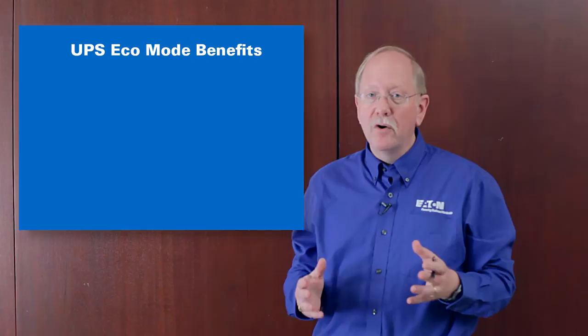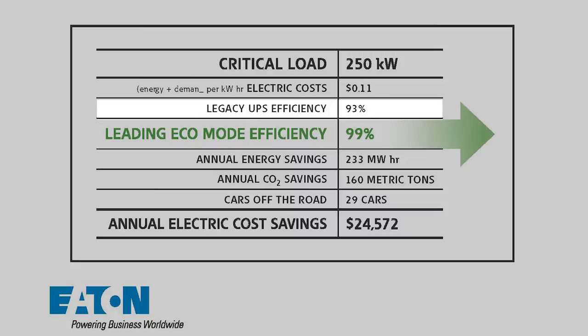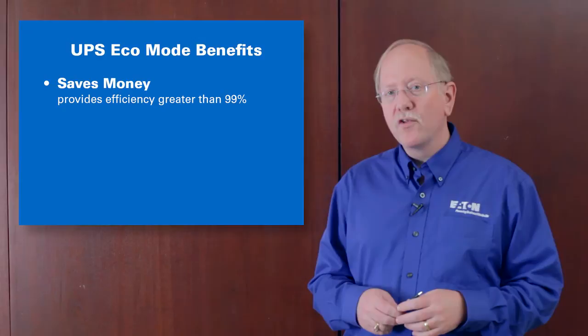The main reason for having eco mode is saving money. So, just as an example, let's take a look at a medium-sized UPS. Here we have a 250 kilowatt UPS, compared against a legacy UPS that's 93% efficient, using an eco mode UPS at 99%, and the savings at 11 cents a kilowatt hour are $24,500 per year of operation. Significant savings, and will actually repay the cost of the UPS within two to three years.